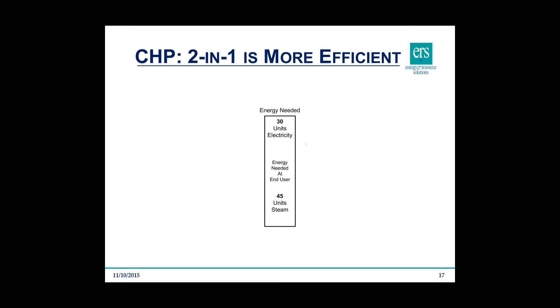Here I've got a theoretical building. Doesn't look like much, I know, but the building will use 30 units of electricity and 45 units of steam. Now, in a traditional generation system, I would purchase my electricity off the grid. The power plant has its own inefficiencies when it comes to producing power, and then I have to get the power to my facility, which leads to some transmission losses. So the overall efficiency of traditional power generation getting all the way to my facility is about 31%. So in order to satisfy my demand for 30 units of electricity, the system will need to burn 98 units of fuel.